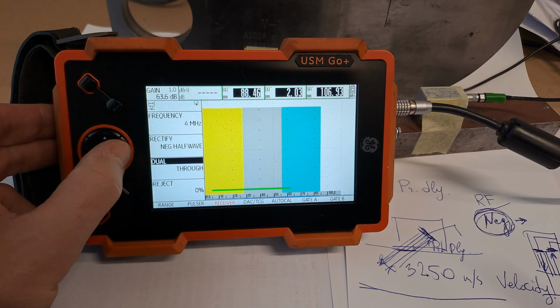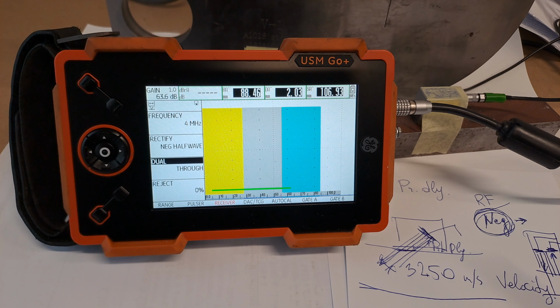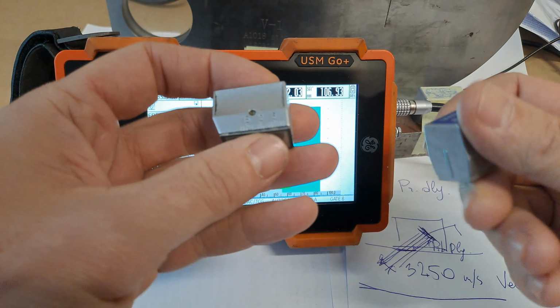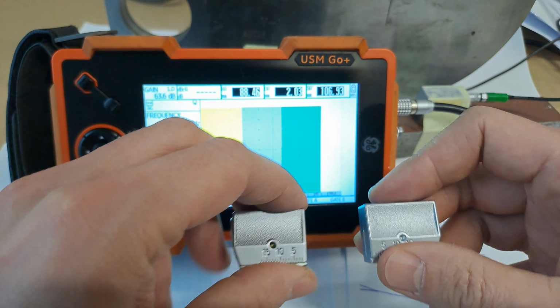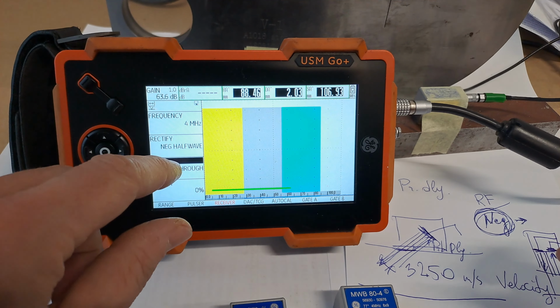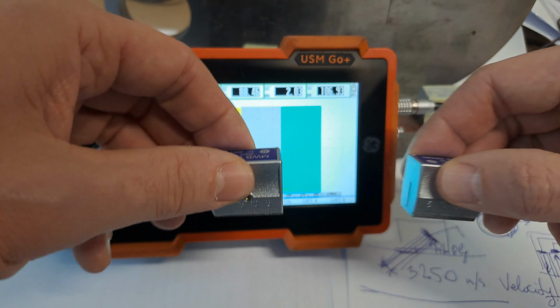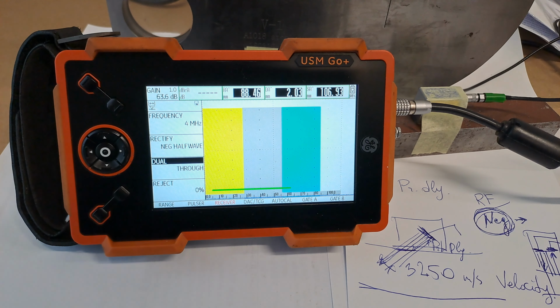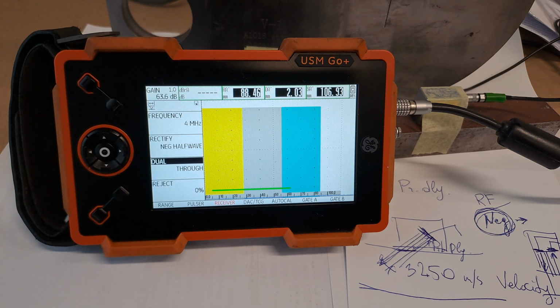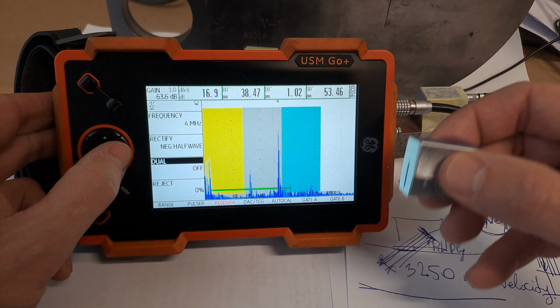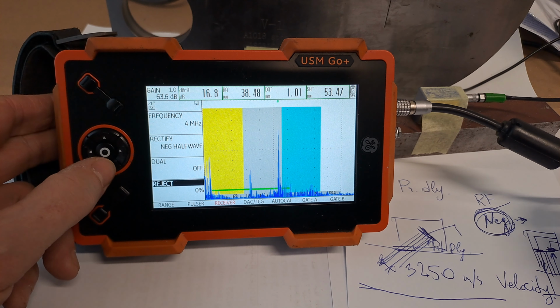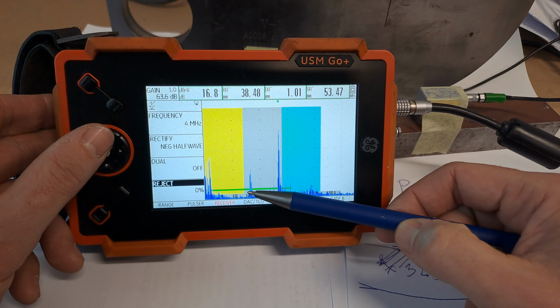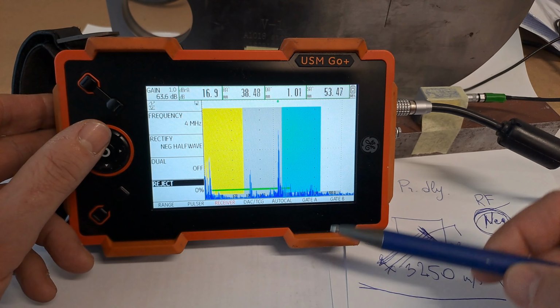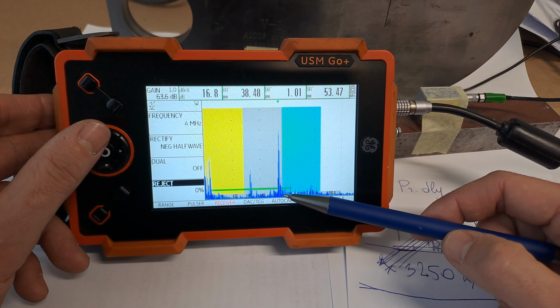And through is what it says, 2 separate probes. So 2 separate probes will do transfer correction. We'll put them like this, and one will be transmitter, one will be receiver, and I think we'll be doing it with a through mode. So one is talking, one is listening. So that's the setting for transfer correction. So for now, for the angle probe, dual is off. Reject is recommended to be 0%, because the noise can be rejected, but we don't reject it. We just ignore the small spikes.